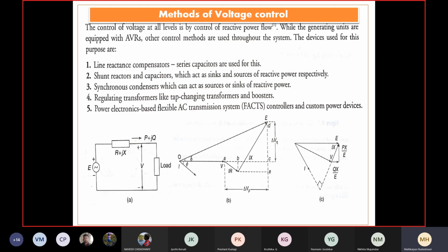So the ultimate aim is to see to it that voltage is maintained within the prescribed working range, plus or minus tolerance. Voltage needs to be maintained in the system. For that, definitely a transformer based approach, where we prefer a tap changing facility with a transformer, makes it possible, or a booster-like transformer, a transformer adding delta V or removing delta V from the line voltage, makes the receiving end voltage shifted or reduced appropriately by the configuration. When we see the diagram, we are able to see the mechanism of a tap changing transformer or a booster transformer in sequence. This is also very interesting.